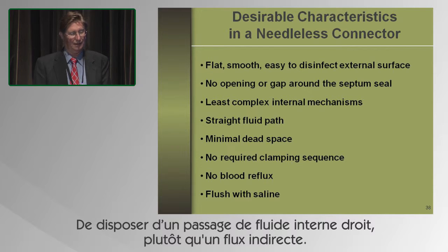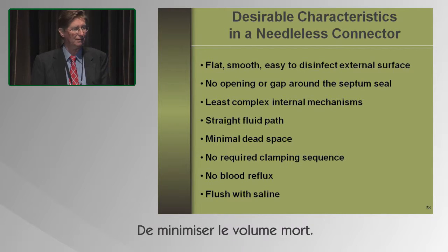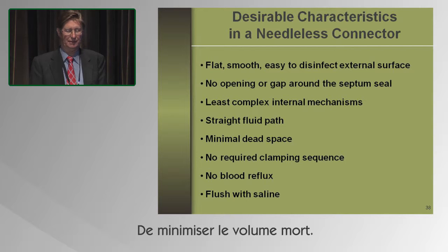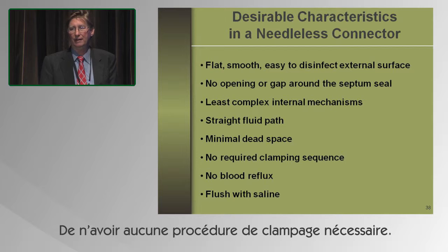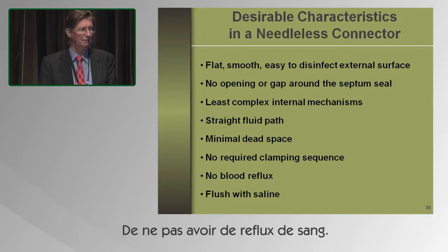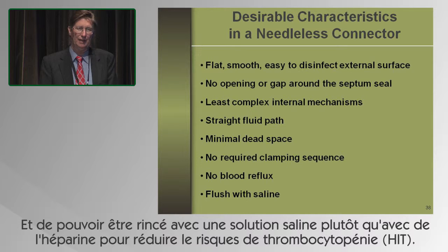To have a straight fluid path rather than an indirect or flow around fluid path. To minimize the dead space. To have no required clamping sequence. To have no blood reflux. And be able to flush with saline rather than heparin to reduce the risk for heparin-induced thrombocytopenia.